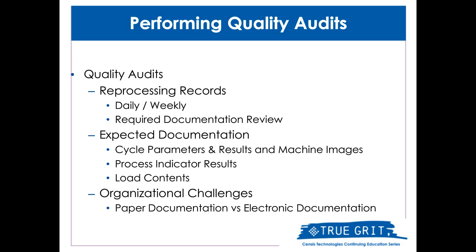All these audits need to review all the expected documentation as laid out by various AAMI standards. We need to capture things like our cycle parameters and results, any sort of machine images, chemical indicator results if applicable, the contents of loads, and if there are any specialized loads like an IUSS cycle, we also need to document a reason for the cycle and the patients associated with that cycle. Being able to access all that information quickly and readily is a fantastic benefit of an electronic tracking system like CensiTrac.